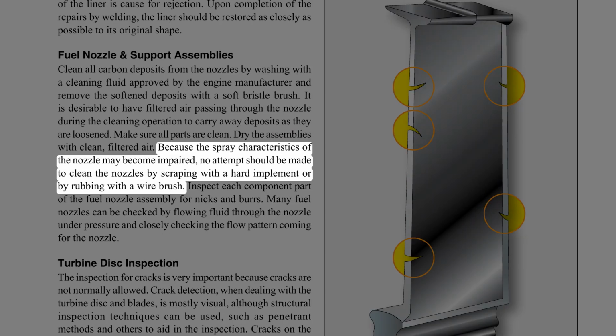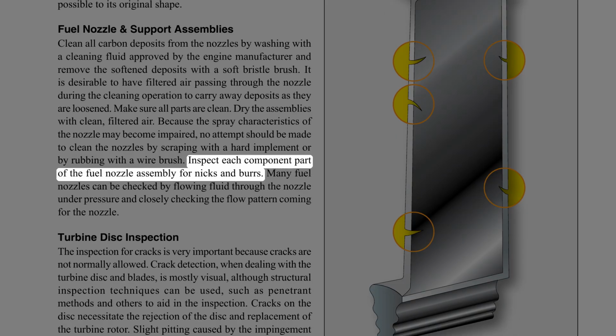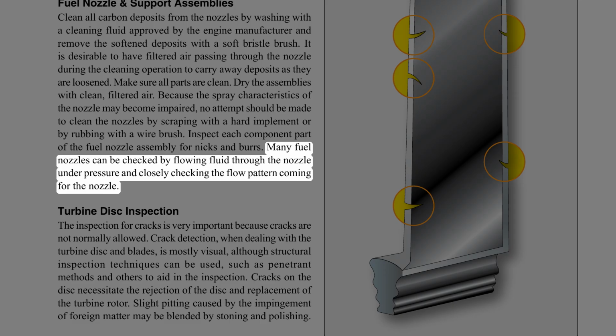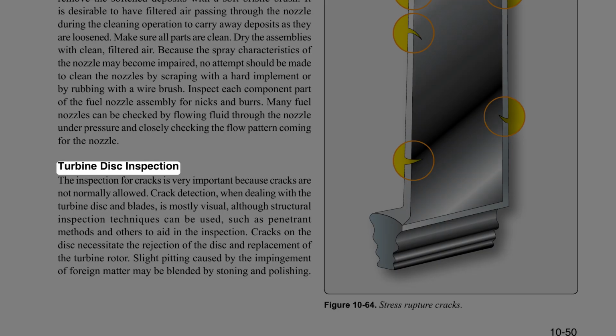Because the spray characteristics of the nozzle may become impaired, no attempt should be made to clean the nozzles by scraping with a hard implement or by rubbing with a wire brush. Inspect each component part of the fuel nozzle assembly for nicks and burrs. Many fuel nozzles can be checked by flowing fluid through the nozzle under pressure and closely checking the flow pattern coming from the nozzle. Turbine disc inspection.